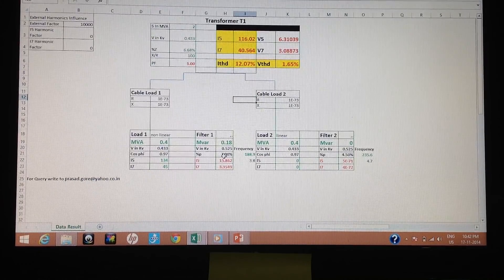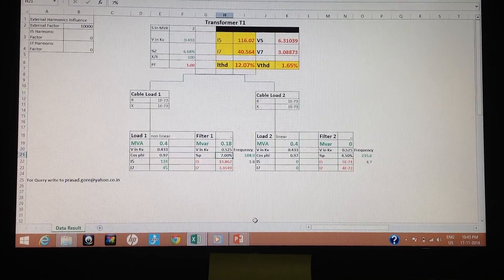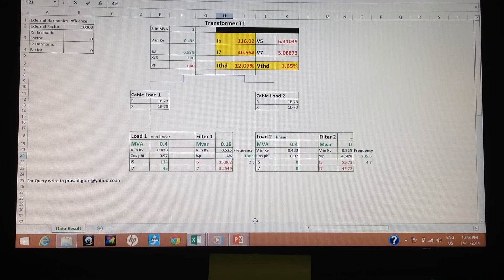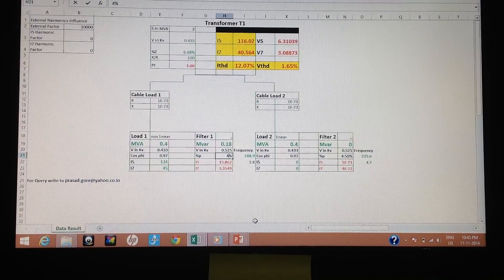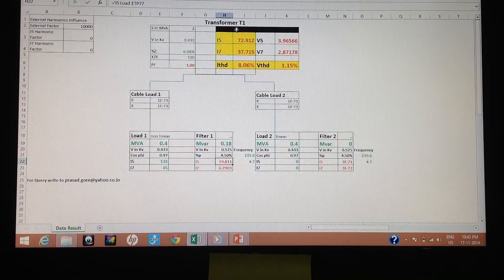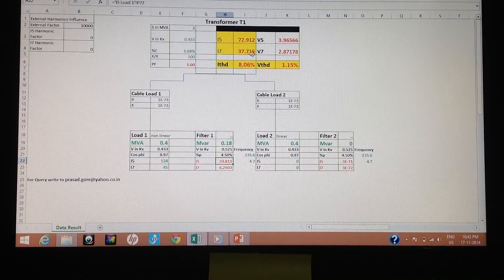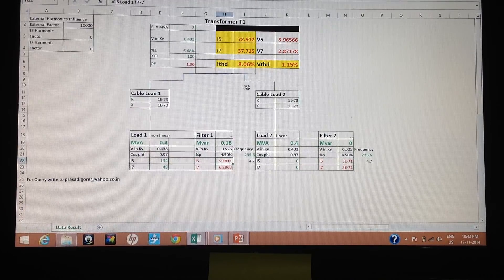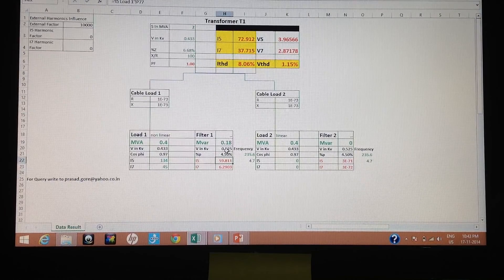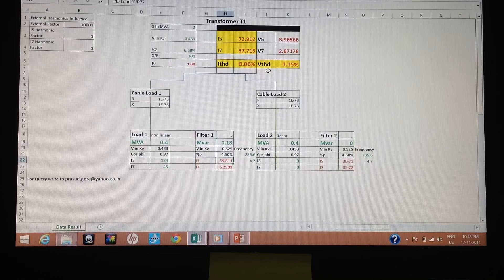To achieve more reduction, we go near the 5th harmonic with a 235 Hz series frequency filter. When there was no harmonic filter, the I5 observed at transformer mains was 131. Now it has gone down to 72. I7 was 43, now it is 37, and the overall Ithd is 8.06 compared to 13.31 without filtering, and 12.07 with the 7% filter. This is a very good reduction that can meet some international standards.